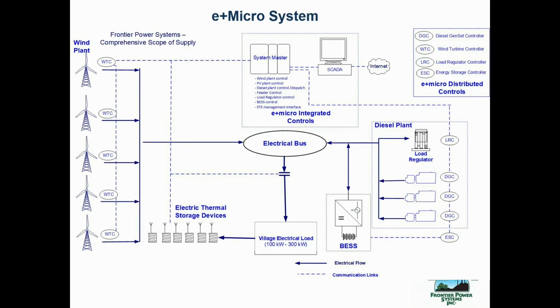I said earlier that our first community was our first medium displacement wind diesel facility. A BESS allows us to go from a medium displacement facility to a high displacement facility. In that first community, no matter how much wind is blowing, the diesels can never shut off because they have to balance frequency and voltage, and they have to be available to come online at a moment's notice if the wind drops. But the BESS does balance frequency and voltage, and can carry the load for a significant amount of time to bring the diesels back up to speed in the event the wind drops off.